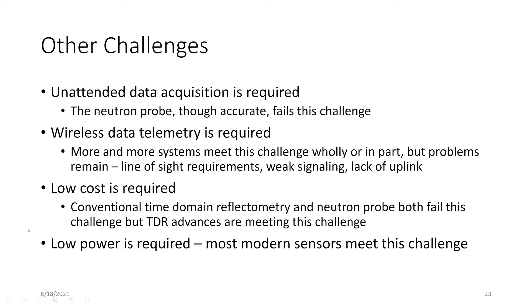meet that requirement. In 2015, we came out with a directly coupled TDR sensor, which combined a computer, a TDR instrument, a probe, and temperature sensor into a single sensor that costs a little bit more than $200. Based on a circuit like this is the first circuit that was developed. It was used in a cylindrical hollow tube for a waveguide on access tube soil water sensing system. And then this circuit was developed to be put into the TDR-315. So this made a great advance in the usability of TDR methods.